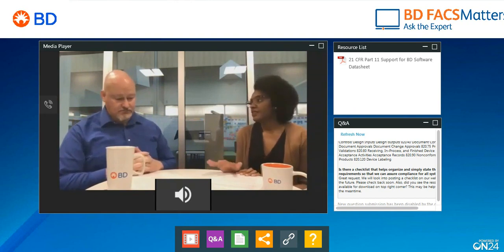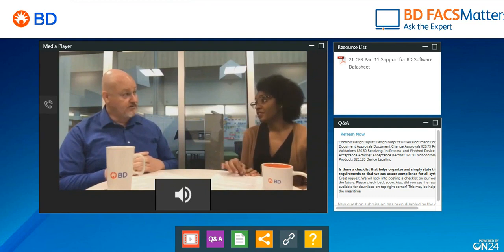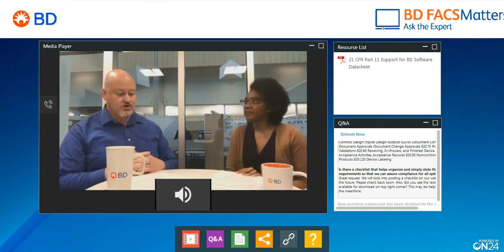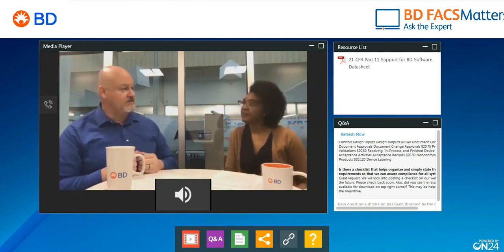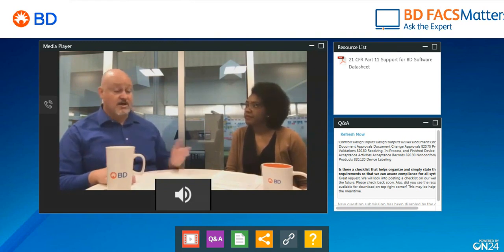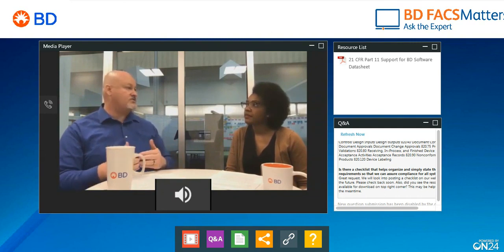One of the interesting things I learned about 21 CFR Part 11 is that it was initiated by the industry. Can you talk a little bit about its background, what it is, and what it requires? Sure. 21 CFR Part 11 covers electronic records and electronic signatures. And as you mentioned, it was requested by the industry pre-1997 when 21 CFR Part 11 was made a law.